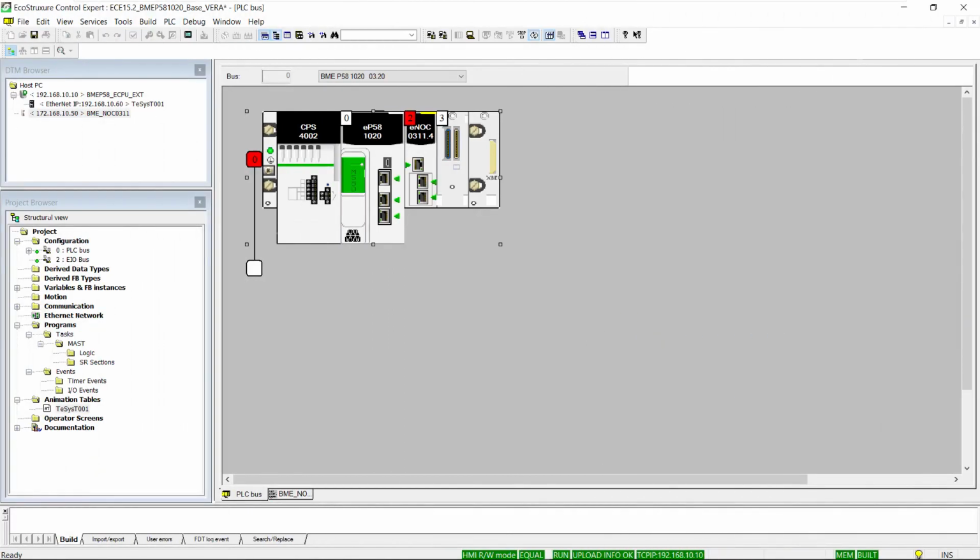Going back to our PLC configuration, it also happens that the CPU and the NOC modules in the M580 controller have the same type of object dictionary. This could be extremely useful to remotely access the identity information of the processor or other modules on the PLC backplane that may not be directly connected to the supervision network.